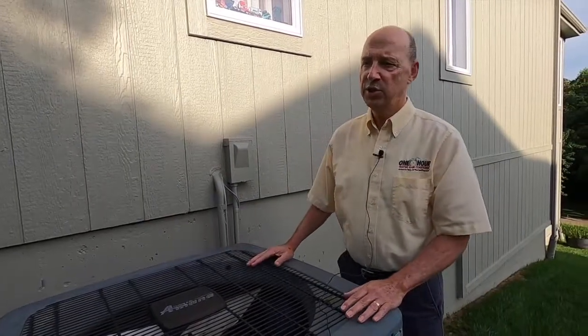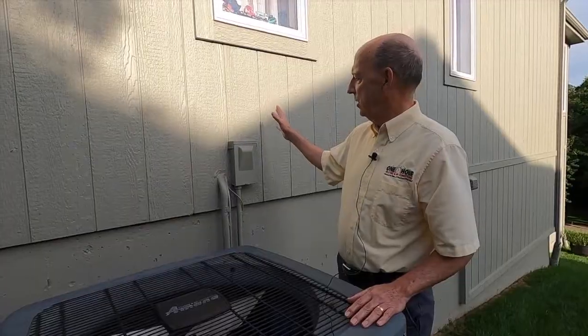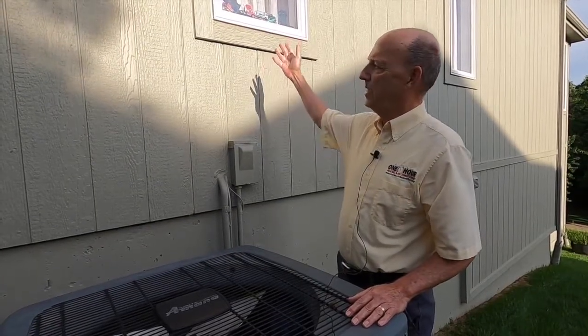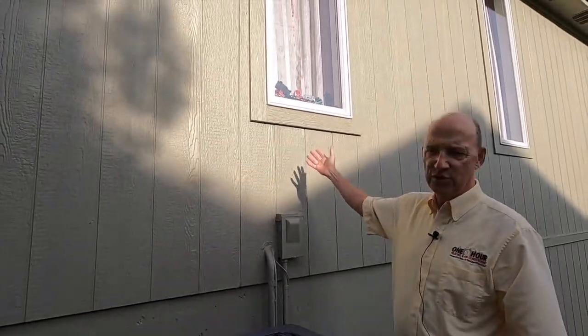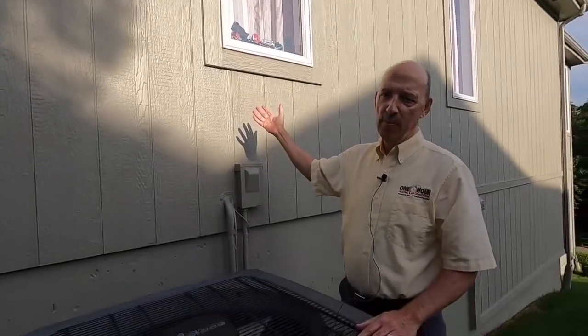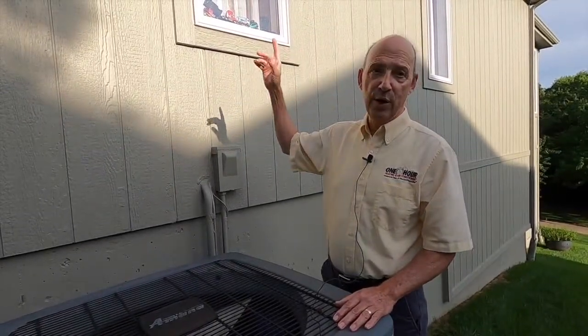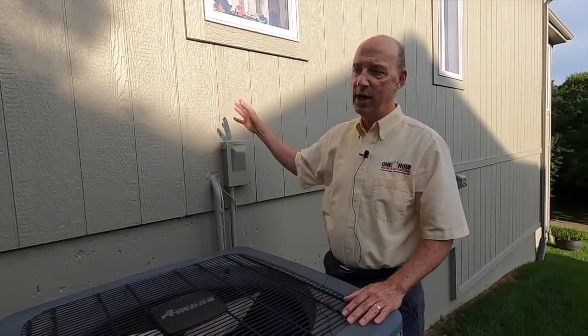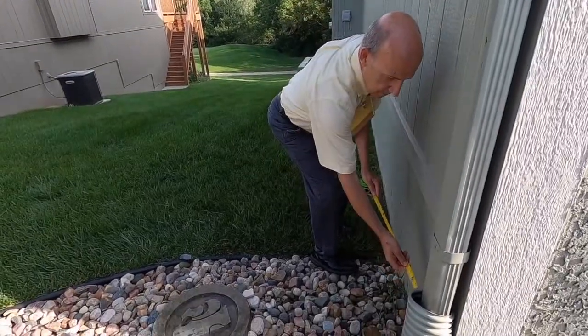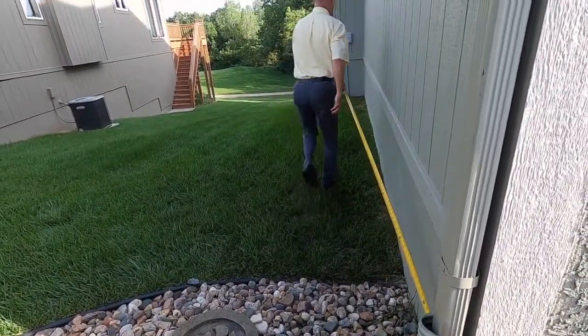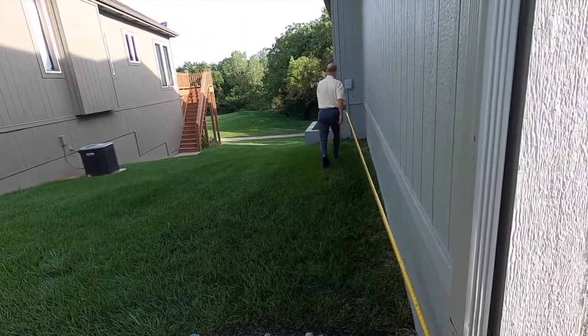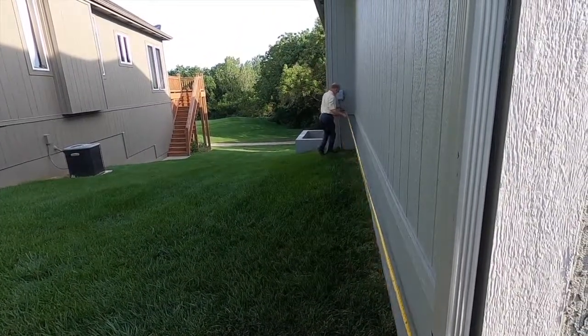What a load calculation does is we will take a house, and as you can see, look what's happening on the side of this house. The sun is starting to peek through, and we've got morning sun on these windows, where on the other side of the house there is total shade. So we go around the house, we literally measure the walls, what direction is it facing, how is it constructed, what kind of insulation is involved in this wall. There are calculations that we can do to properly size the air conditioner, but it's extremely important to do that.